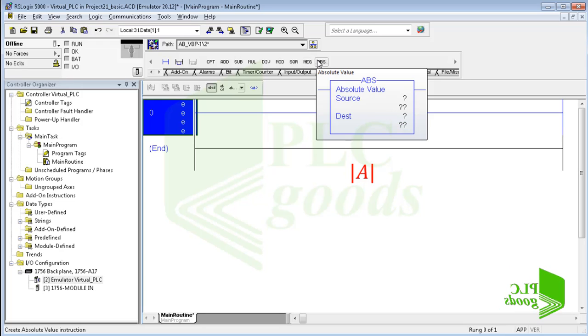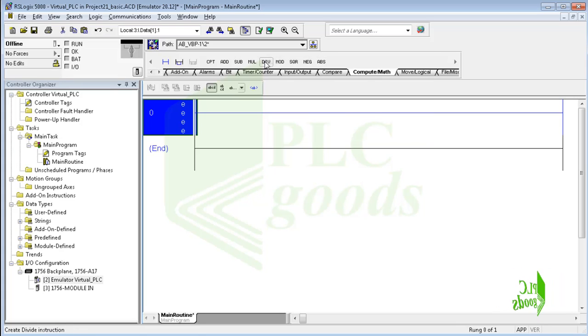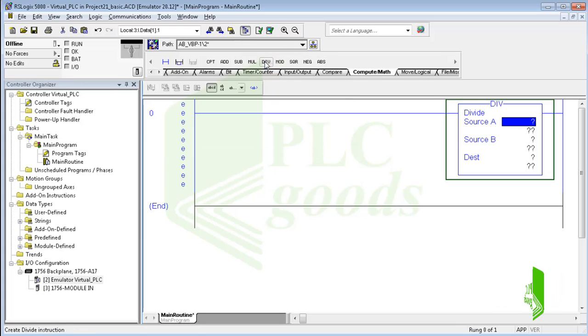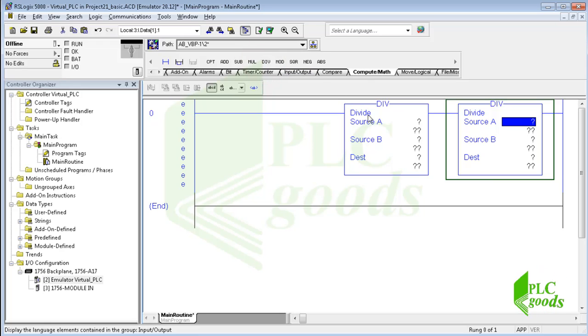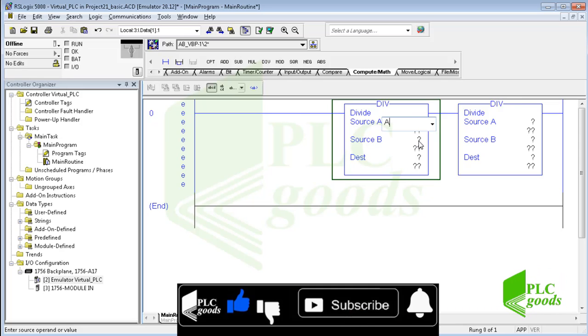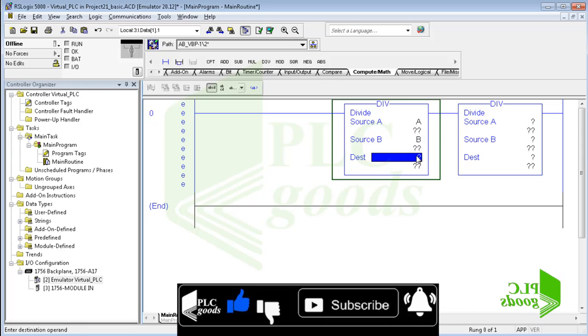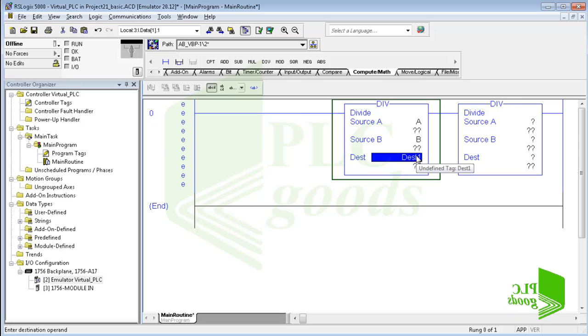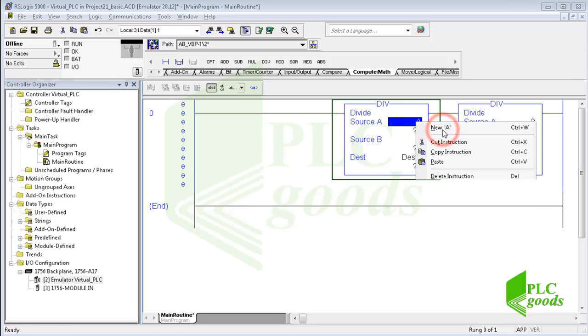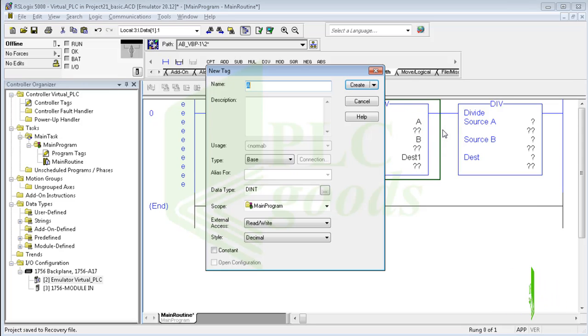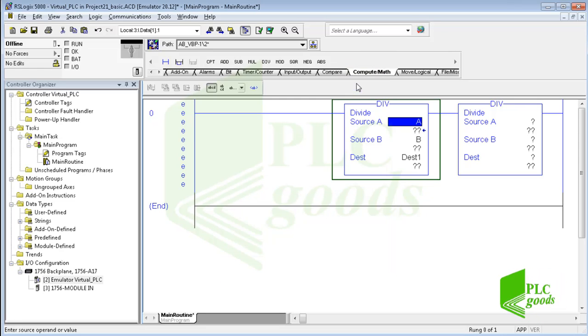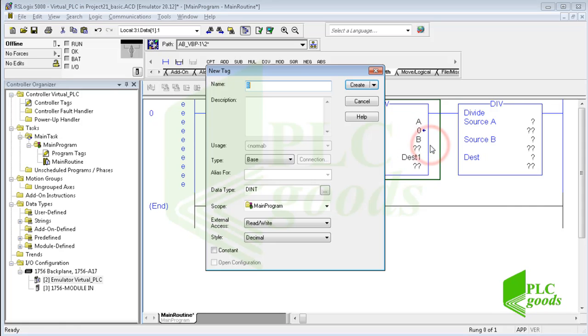Let's use the division instruction to learn how we can use basic math instructions. First I must determine what our source A and source B values are. Here I can enter constant numbers or use tags which store a number. Also I must determine where the result must be saved. I want to use tags which their values can be changed, so let me right-click on each tag and click on new. Usually double integer or real numbers are used for math instructions. Now let me use double integer data type.